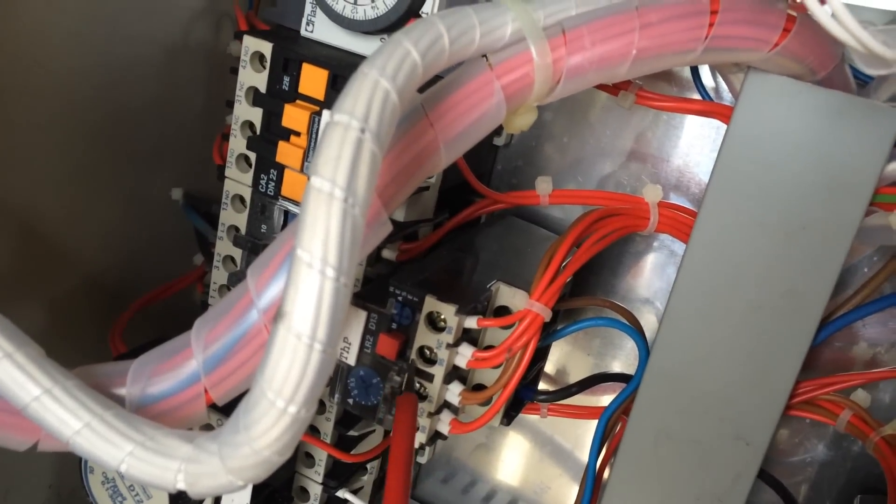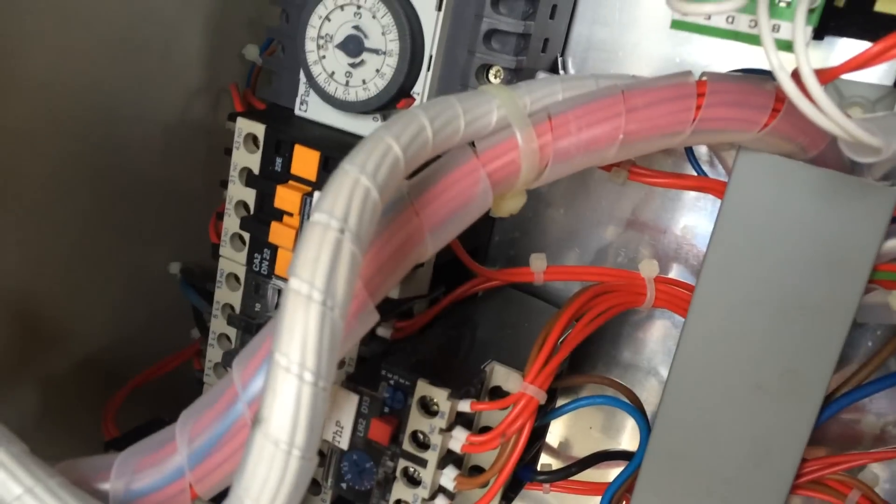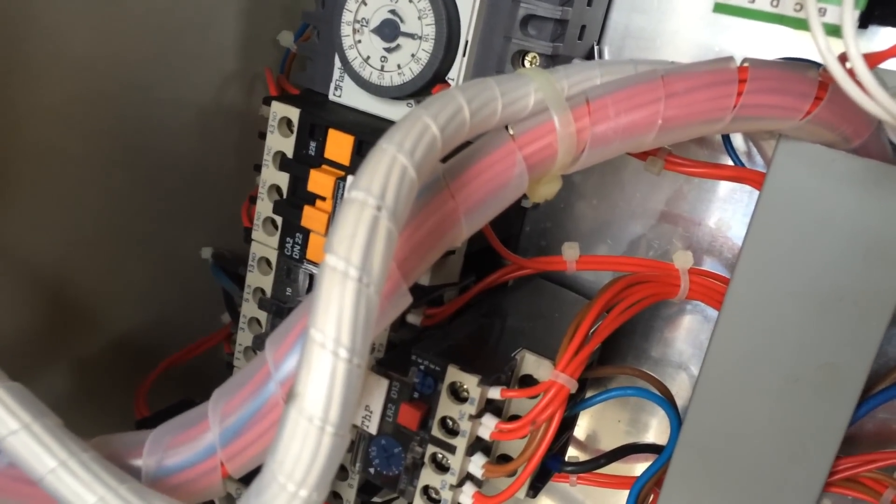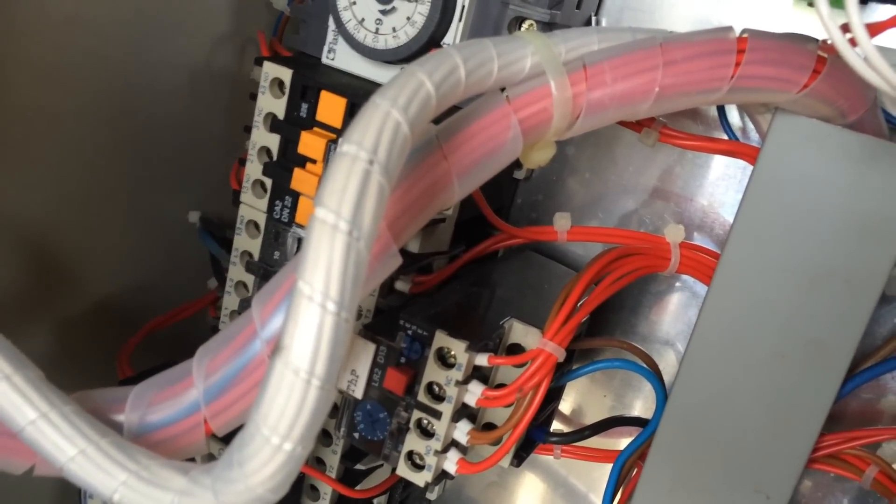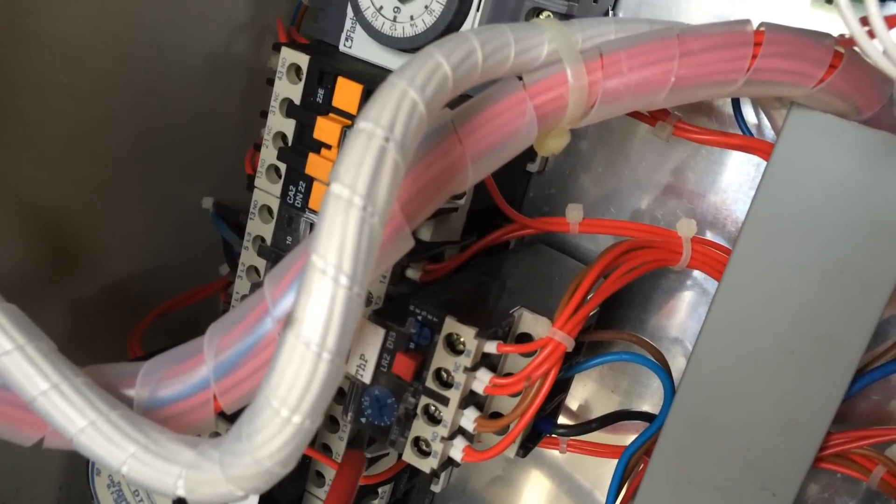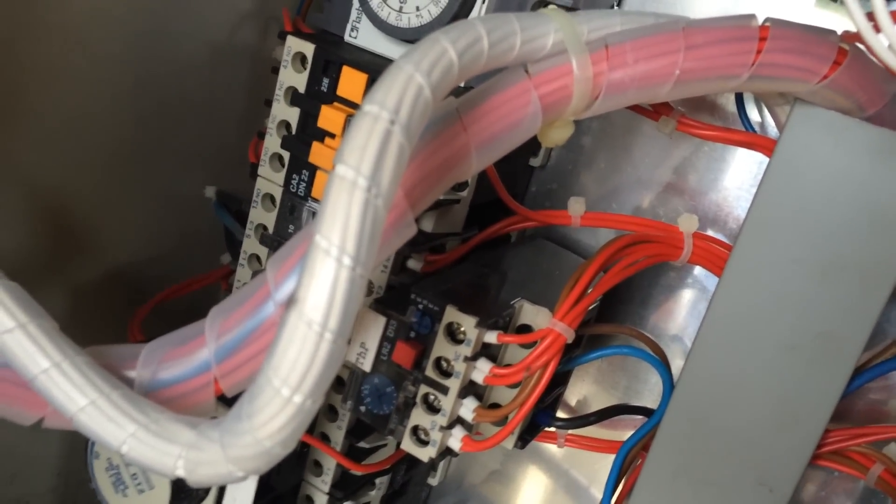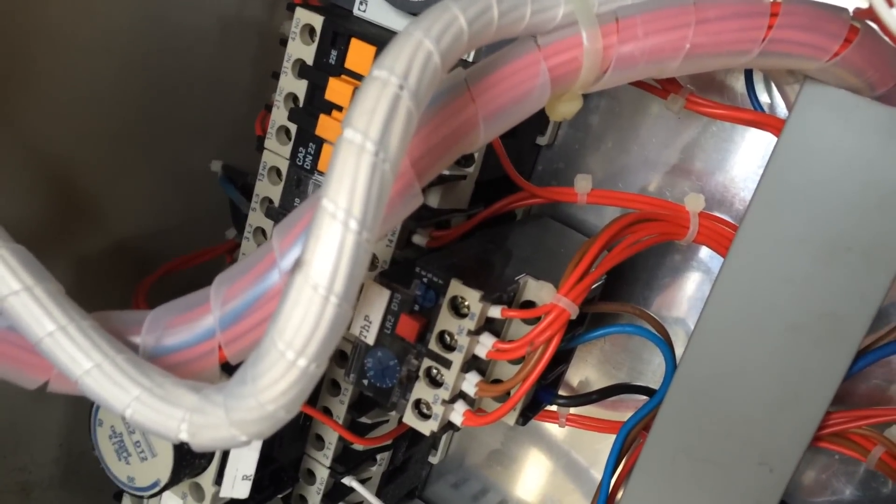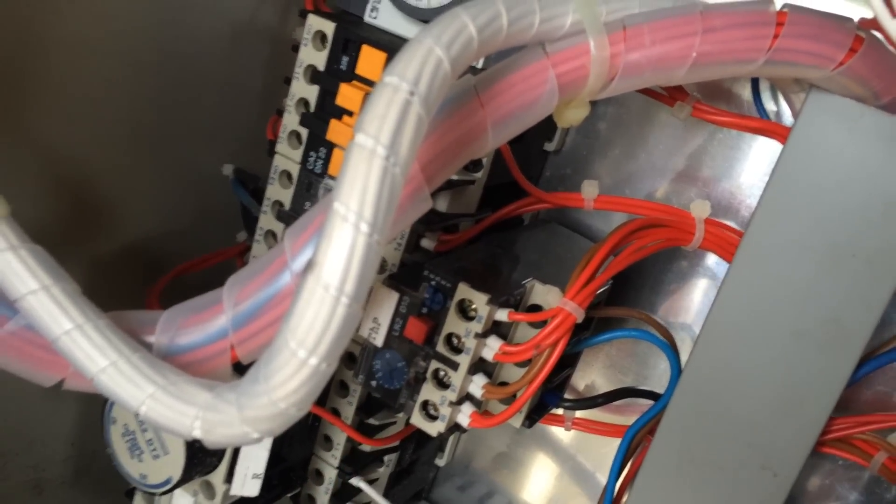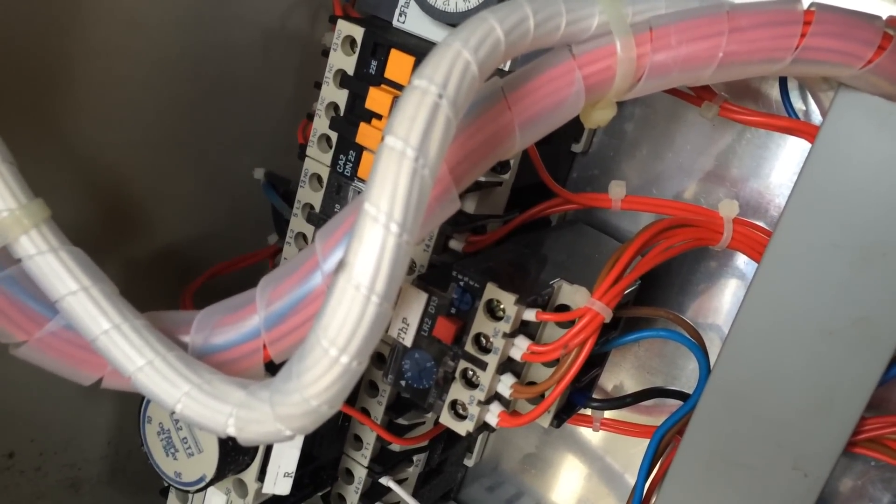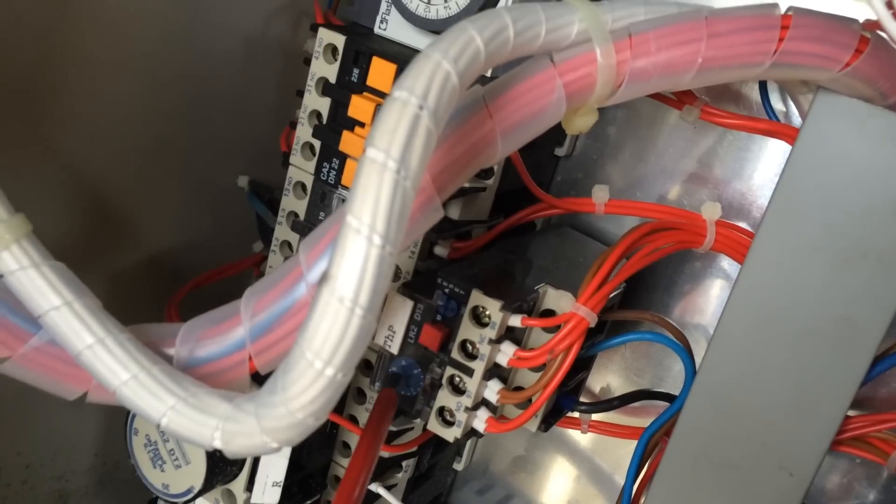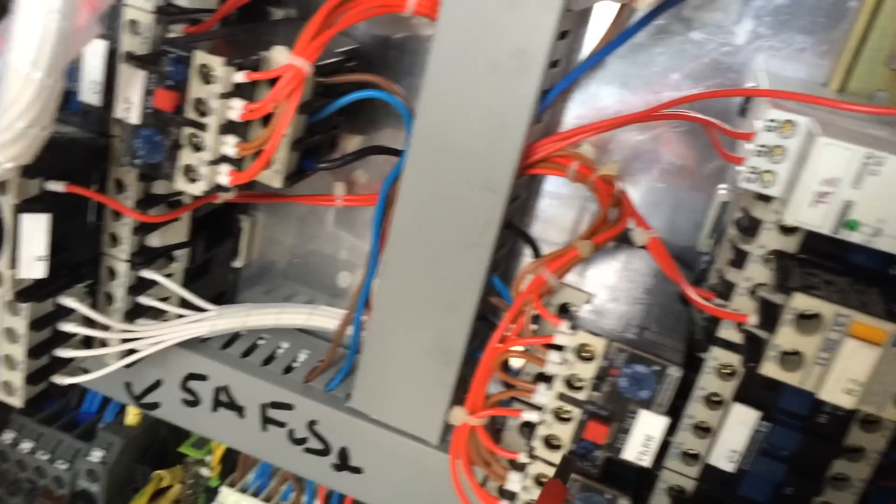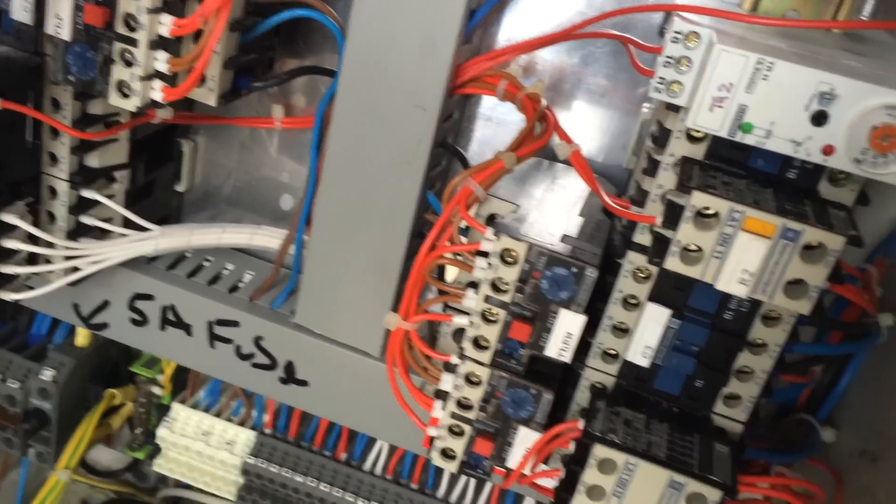So if there is a problem with one of the motors, it tends to stop everything for a few minutes to cool down and then reset, and off it goes again. So that can mask the issue a bit, because normally they'd trip and stay tripped and you'd know what caused the problem. But you can get things that end up tripping and resetting while nobody's watching, and then you're not aware of what's going on. But that is something to be aware of. A lot of these come out of factory set on automatic reset.